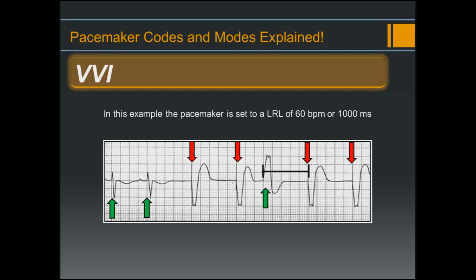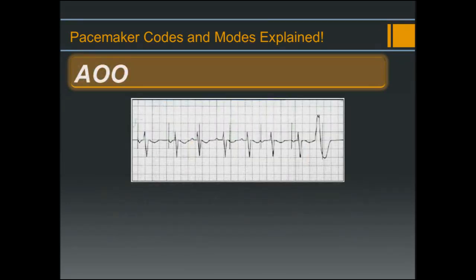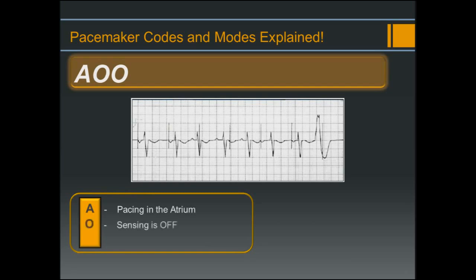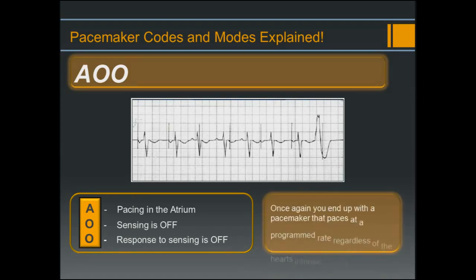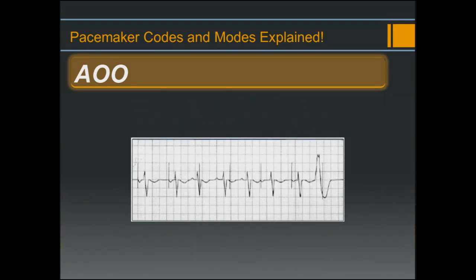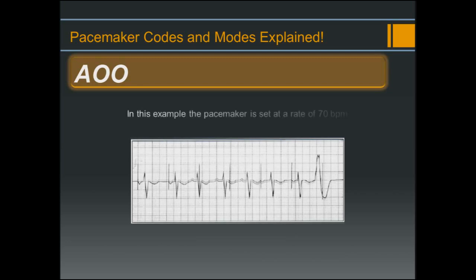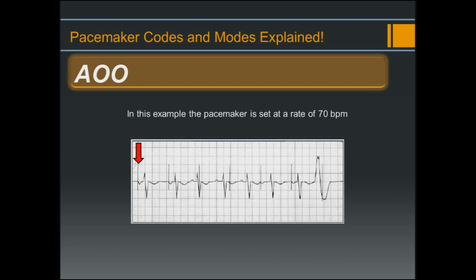It's easy to see that VVI mode is more capable than VOO — we are only pacing the heart when there's an absence of intrinsic activity: pace when you need to, but not when you don't. AOO mode: pacing in the atrium, sensing is off, and a response to sensing is off. The pacemaker paces at the programmed rate regardless of the heart's intrinsic activity. In this example at 70 beats per minute, if atrial sensing were turned on, the pacemaker would have seen the atrial beats marked by the green arrows.